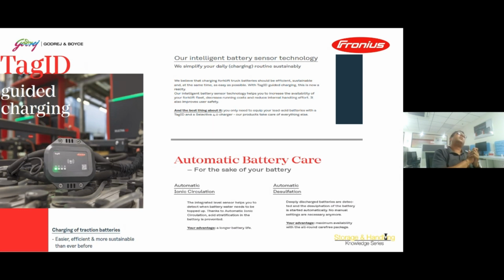Second advantage: sometimes because of improper use of the battery - opportunity charging, abuse to the battery - the battery doesn't get a proper equalized charge. If charging wasn't proper before and we newly adopt RI charging with tag ID on the battery, where earlier conventional charging was there, once this system is adopted, if the battery is sulfated or some cells have gone to deep discharge, the tag ID will automatically sense this condition and instruct the charger that this battery is under threat of deep discharge or sulfation, and the charger will automatically start reducing that sulfation.